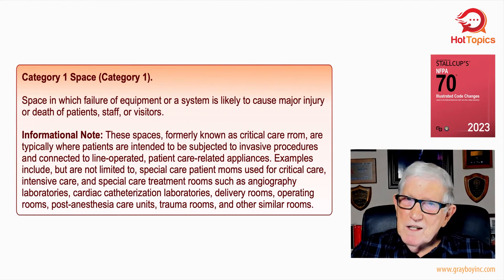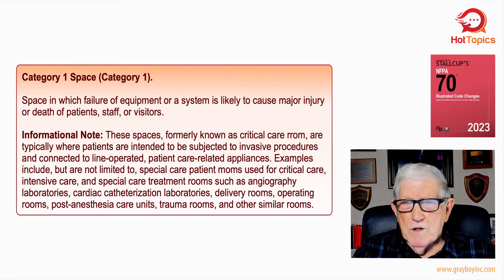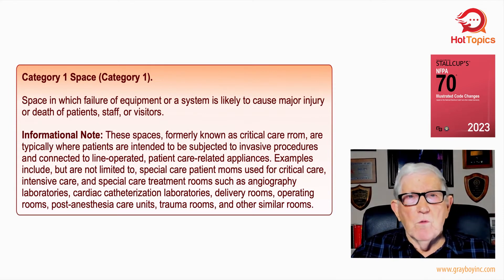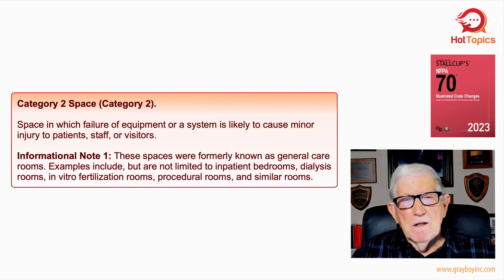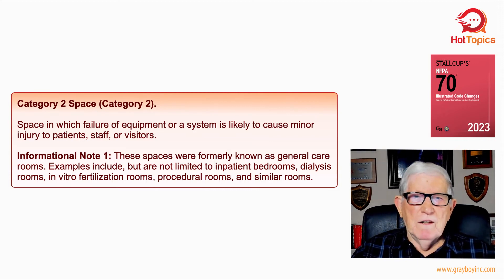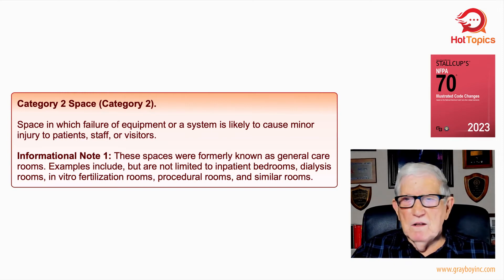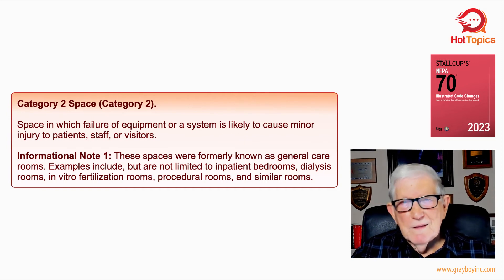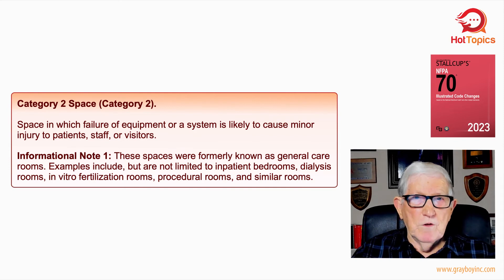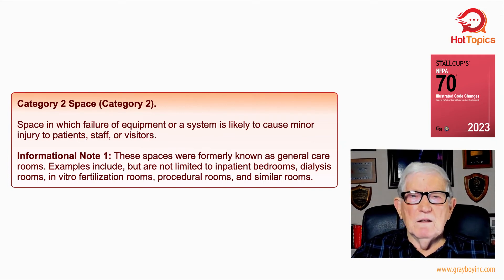So they're saying these receptacles are limited to these areas, or a similar area where the engineer designates it as such, or a contractor doing the work — subject to the approval of the authority having jurisdiction. Category 2 is a space in which failure of equipment or system is likely to cause minor injury to patients, staff, or visitors. These spaces were formerly known as general care rooms, and examples include — but are not limited to — inpatient bedrooms, dialysis rooms, and similar rooms, designated by an engineer or contractor having authority, always subject to approval of the authority having jurisdiction.